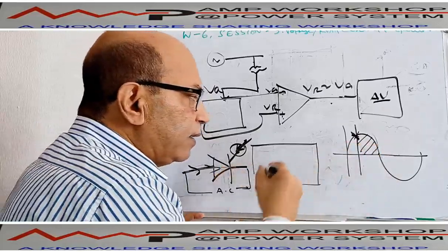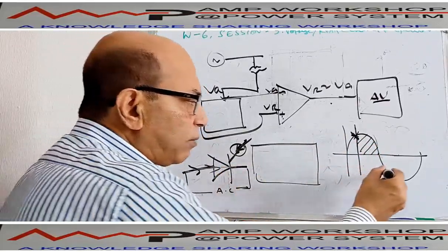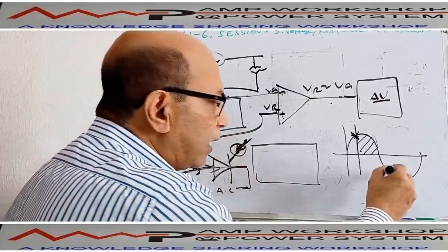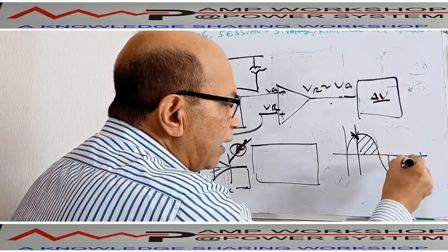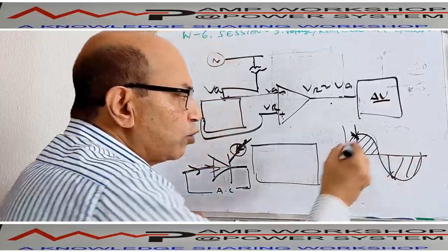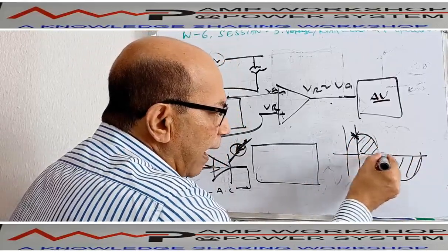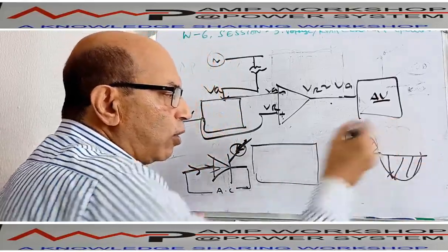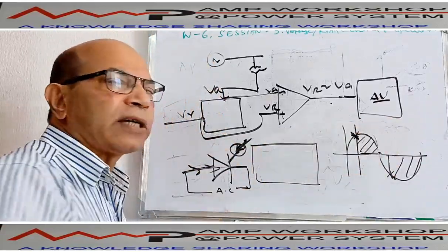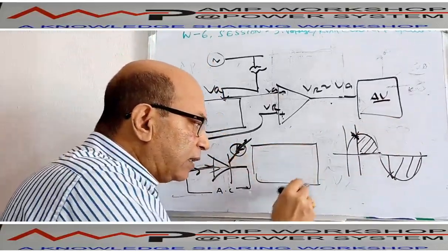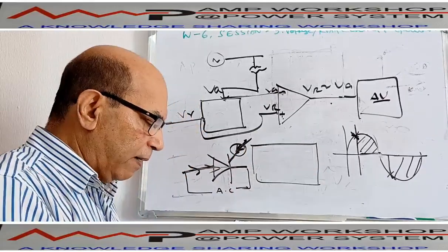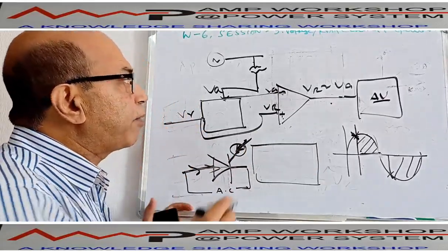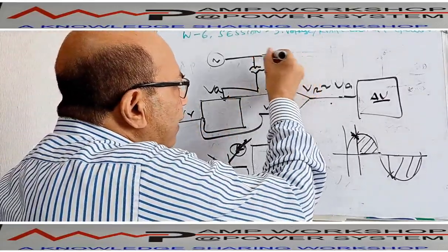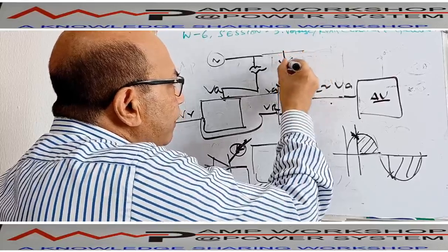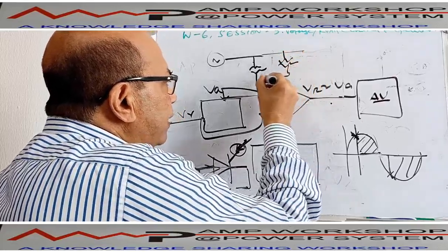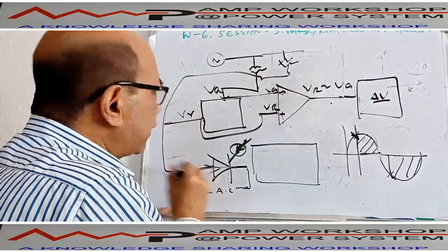Then again, a second trigger comes; suppose there is a reverse, another diode there. At that point we trigger, then this amount of current will flow. So by controlling this angle, we can control the output power of the thyristors. This thyristor is located inside the power block, and where is this thyristor getting power from? Here we are putting another voltage transformer. This voltage transformer is giving power to this thyristor block.